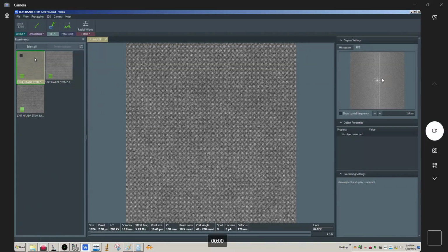So this really isn't an issue so much with a TEM series, but this can be an issue with STEM because it's a serial process and it can take a significant amount of time per frame to record each frame, okay? So that's why this tends to be more of a problem with STEM and specifically with atomic resolution STEM with a periodic structure, okay?